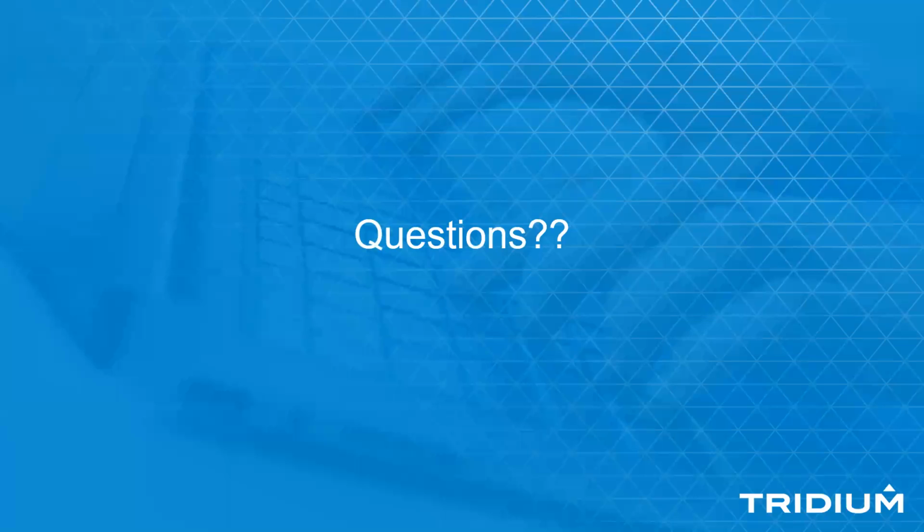Philip Moody has a question. He just wants some clarification. If he has a supervisor running 4.10, but his Edge 10s are at 4.7, and the graphics are being served from those 4.7 graphics, they can't be UX. That's correct, Philip. In order to utilize UxMedia, you will need to be at 4.10, unless, of course, your graphics are resident on your supervisor. If they are indeed resident on your supervisor, then you can convert those graphics accordingly, provided that your supervisor is at 4.10.